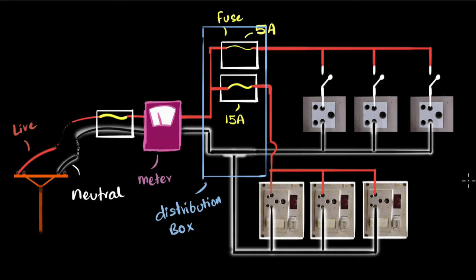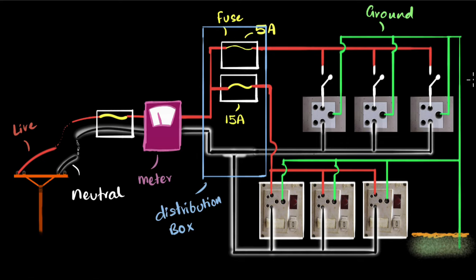The third hole is connected to a green wire which eventually goes to the ground. Look at that - all the connections eventually go into the ground. That's why I call it the earth wire, or you can call it the ground wire. What does it do? Well, it produces a very low resistance path for that leaky current, which means if the current is leaking, it doesn't flow through you because you are much higher resistance compared to this wire. So the current will flow through this wire. It will protect you and it will make sure the current safely goes into the ground.